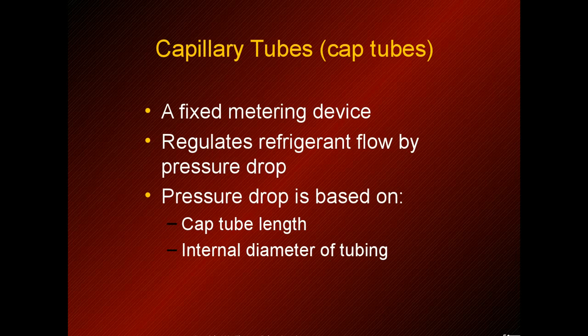The capillary tube falls in the category of a fixed metering device, and like all metering devices, it regulates refrigerant flow by dropping the pressure. Unlike a fixed orifice or a TXV, that pressure drop is determined by the length of the cap tube and the diameter of the cap tube.